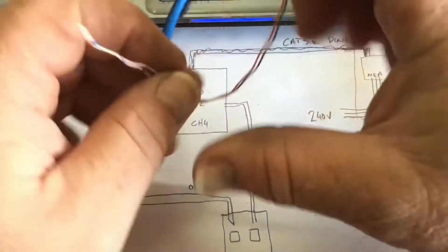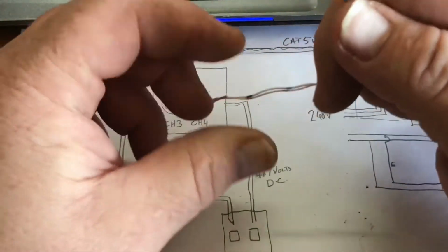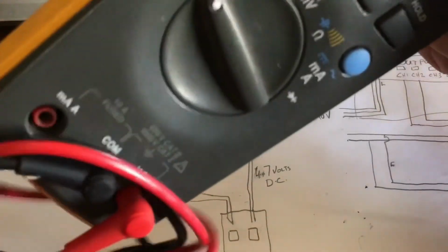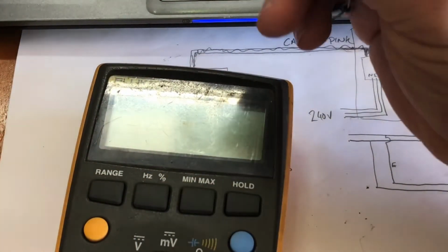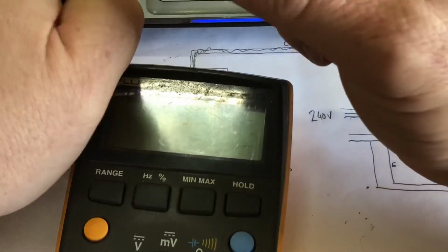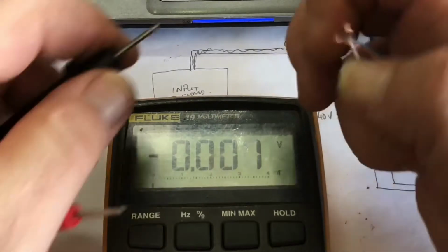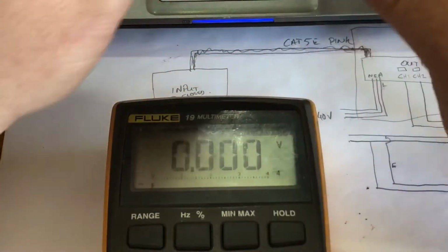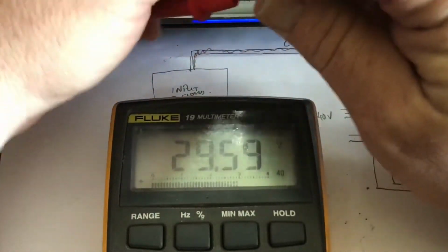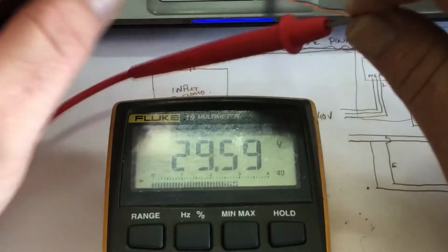And just to show you that it's all low voltage stuff, I'll plug this into the network. So this is the Cat 5 CBus cable, and I'll show you it's only about 32 volts. It might be a bit less here, because this is the very, very last thing along the cabling from where the power supplies are located. Hopefully you can see that. It might be only about 28 or 29 volts. Let's find out. Here we go, 29 volts.